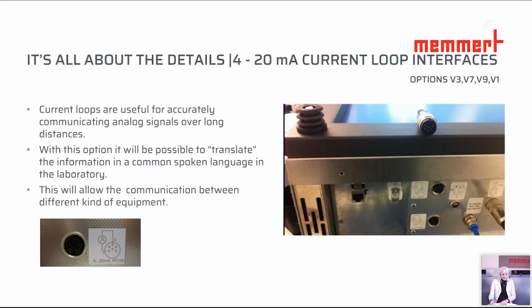So for this current loop interface, we have here V3, V7, V9, and V1. And this refers, for example, to 4 to 20 milliampere in regard to the temperature controller. This means if we consider an incubator with temperature from 0 to 70 degrees, then 0 degrees is the signal for 4 milliampere, and 70 degrees is for 20 milliampere. If we consider the assignment, it also refers to the humidity controller. Here we have from 0 to 100%.